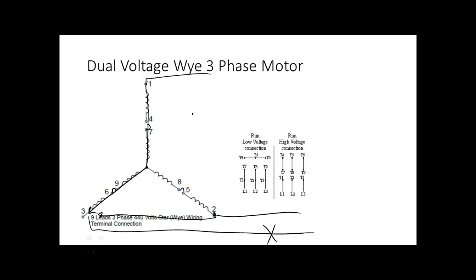A 5 horsepower motor is going to do everything it can to develop 5 horsepower. So if you lose current flow in one phase inside that motor, the other 2 phases will try to make up for it.